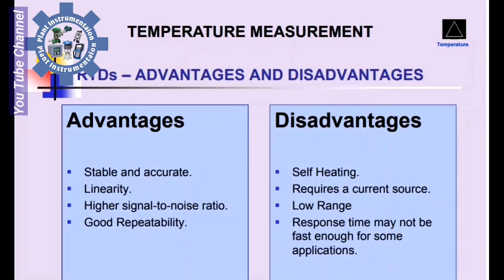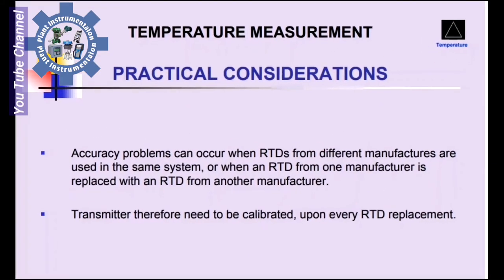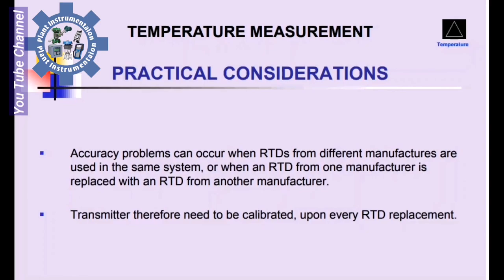RTDs: Advantages and Disadvantages. Advantages: stable and accurate, linearity, higher signal-to-noise ratio, good repeatability. Disadvantages: self-heating, requires a current source, low range response time may not be fast enough for some applications. Accuracy problems can occur when RTDs from different manufacturers are used in the same system, or when an RTD from one manufacturer is replaced with an RTD from another manufacturer. The transmitter therefore needs to be calibrated upon every replacement.